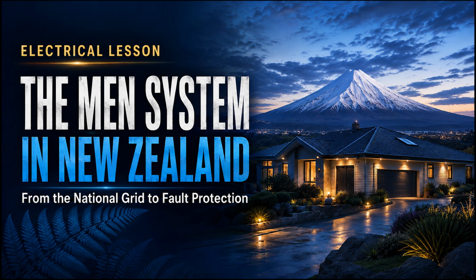Before moving on, we need to clear up one of the most common sources of confusion: the difference between the metallic fault current path and the path through the soil. The word earth can cause confusion. Students often imagine that every earth fault current travels down the local earth electrode through a large distance of soil and then back to the transformer electrode.